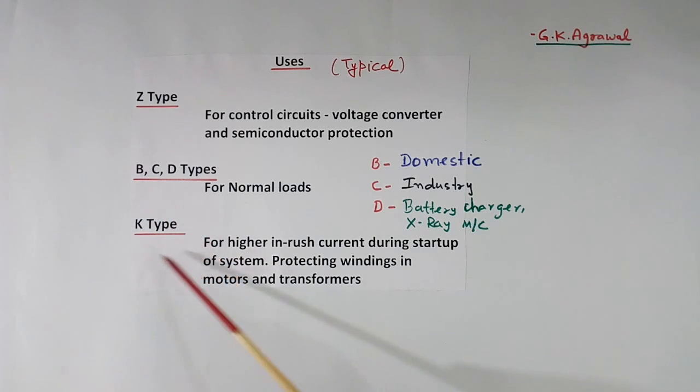K type is used when higher inrush current during start up of system is there. For example in motors and transformers. When we switch on, heavy inrush current flows. There we use K types.